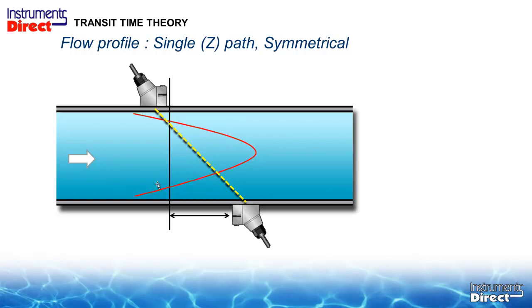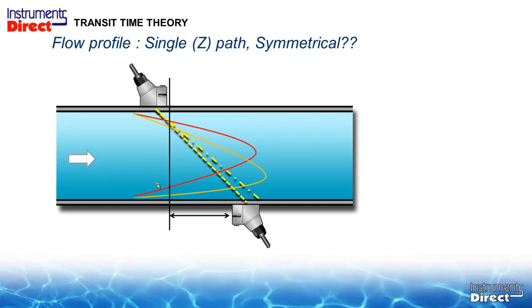performance. But if you have less than a straight run of pipe, you get a disruption in the flow profile, and guess what? It may actually skew where the exit point of the signal would be. So that being the case, your transducer may not even pick up the signal. And so if you have to find the signal, you may actually have to move the transducer upstream or downstream in a prospecting fashion to find the signal. But once you do that, you may get a signal, but it will not be at your optimum accuracy.